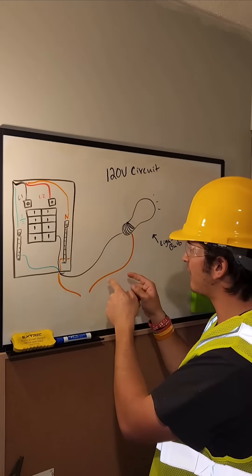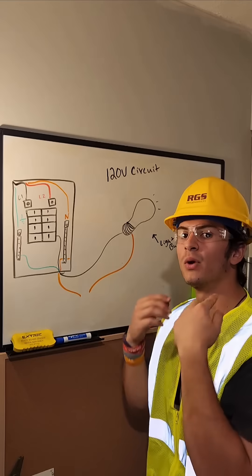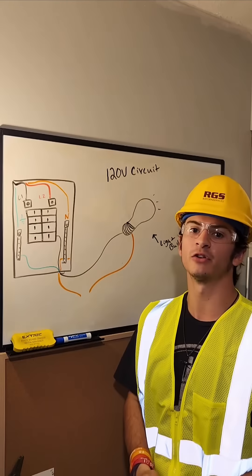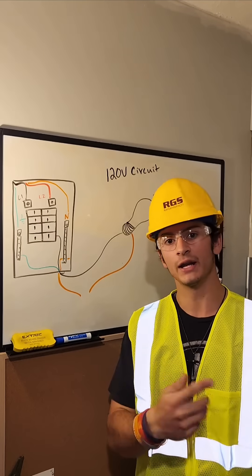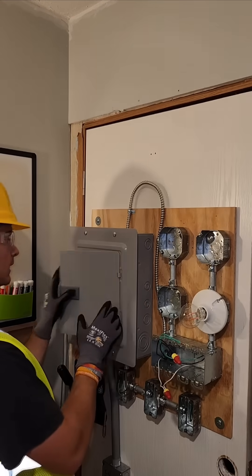So now when measured to ground it's going to have 120 volt potential when in normal operating circumstances it should have zero. And now I'm going to illustrate that on the board. Let's turn on our light.